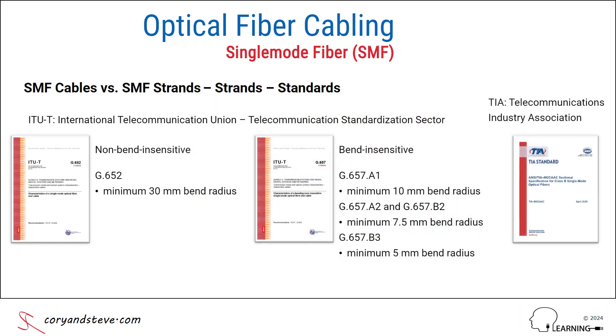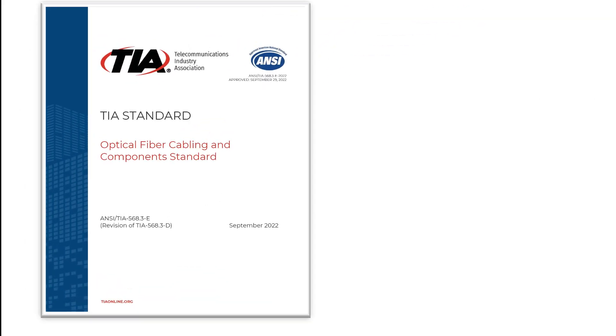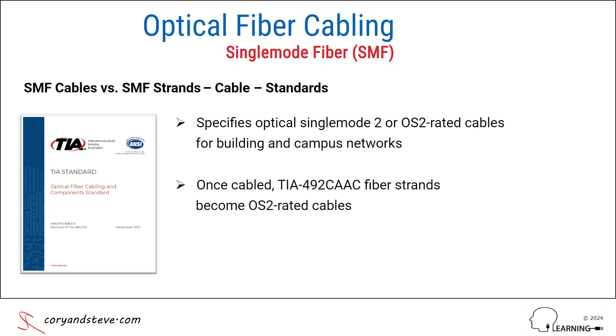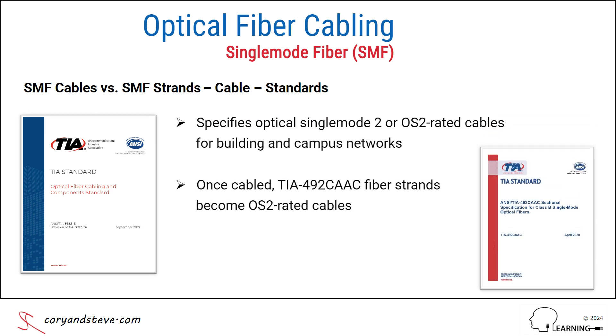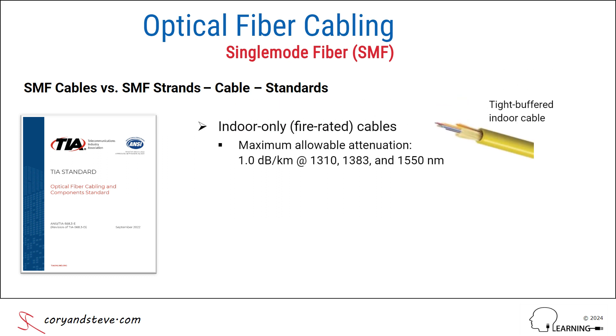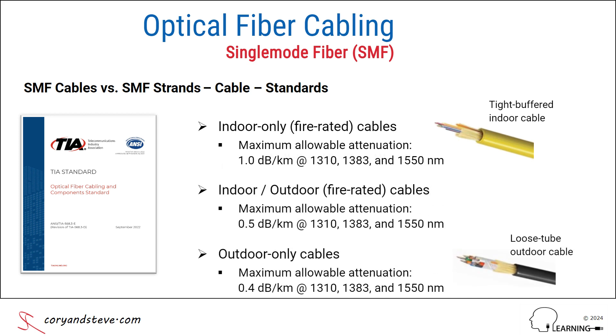Let's now move on to single-mode fiber cable standards. The TIA-568.3 standard, currently in Edition E, specifies the use of optical single-mode 2 or OS2-rated cables for building and campus networks. The fiber strands within these cables are specified in TIA-492 CAAC, as described previously. The optical loss or attenuation performance of an OS2-rated cable depends on its construction. Tight-buffered indoor cables have higher allowable losses than loose-tube outdoor cables, with indoor-outdoor cables somewhere in between.